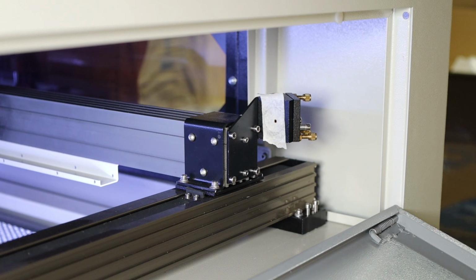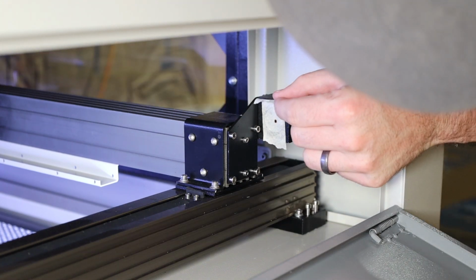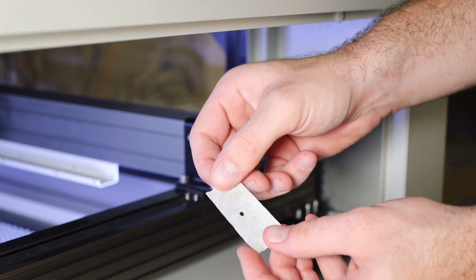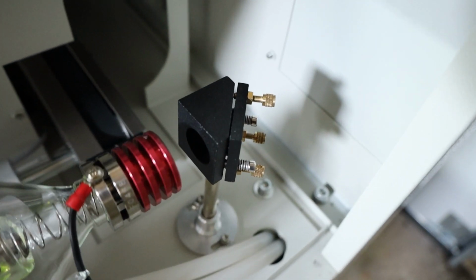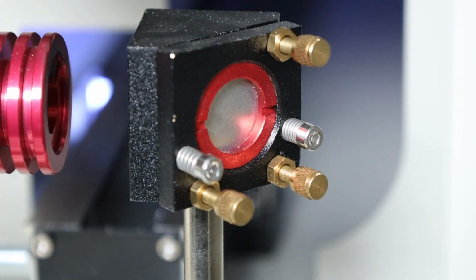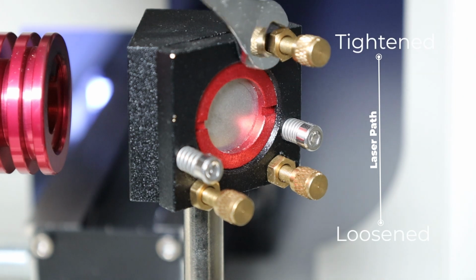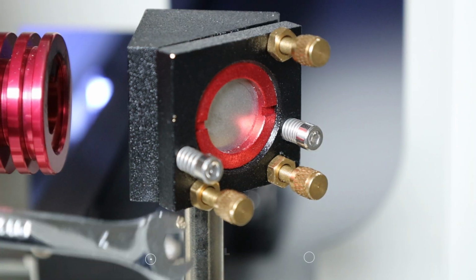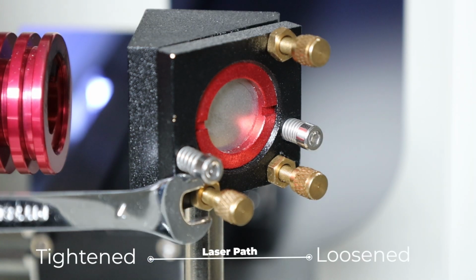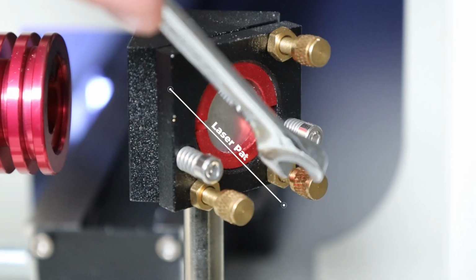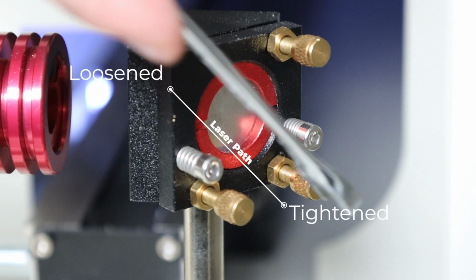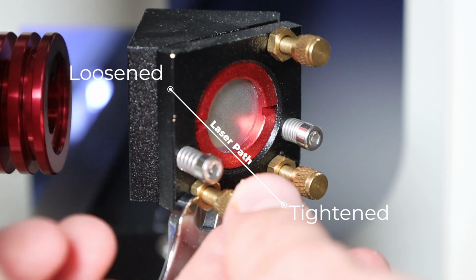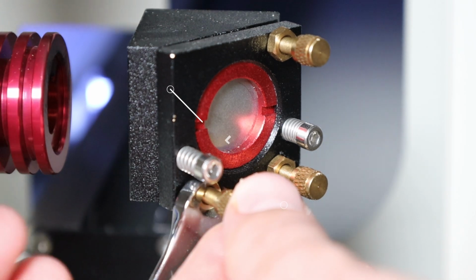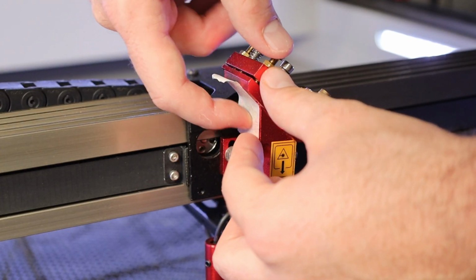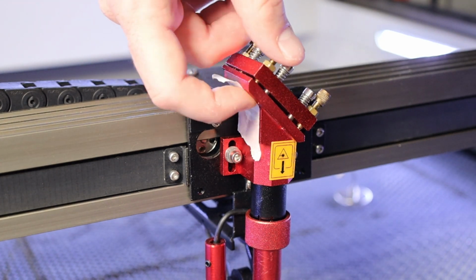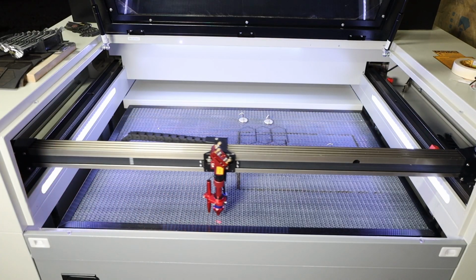This time, if the dot is off center, it's a little bit more confusing to adjust, but it's still not too bad. Each mirror is mounted on 2 spring-loaded bolts and angled with 3 thumb screws. The top thumb screw moves the laser path up when tightened and down when loosened. The left bolt moves the laser path left when tightened and right when loosened. The last middle bolt moves the laser path diagonally. Tightening it moves the laser path down and right, while loosening it moves the laser path up and left. If everything looks good, repeat this process for the second mirror, making sure to test on both the far and near side of the axis.